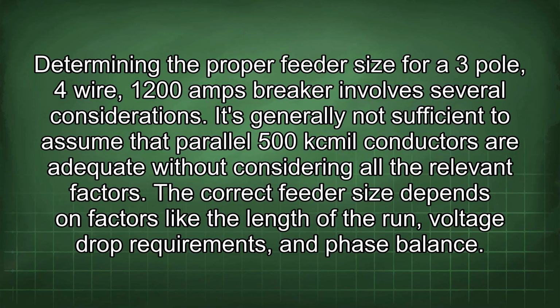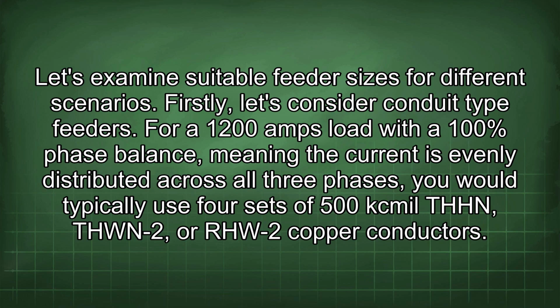Determining the proper feeder size for a 3-pole, 4-wire, 1200 amps breaker involves several considerations. It's generally not sufficient to assume that parallel 500 kcmil conductors are adequate without considering all the relevant factors. The correct feeder size depends on factors like the length of the run, voltage drop requirements, and phase balance. Let's examine suitable feeder sizes for different scenarios.